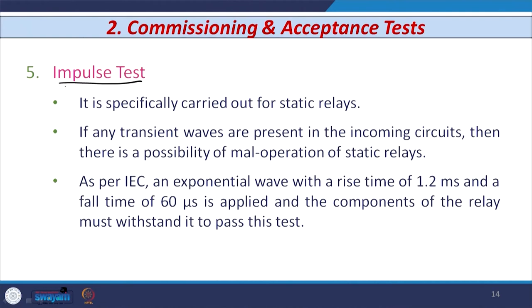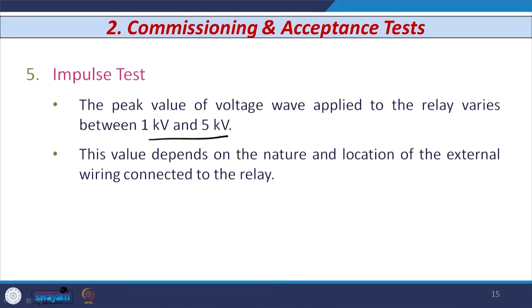The fifth type of test is known as the impulse test. This is a special test carried out on static relays — it is not performed on electromechanical relays. If any transient waves are present in the incoming circuit, there is a possibility of mal-operation of the relay, so this test is carried out to avoid that. An exponential wave with a rise time of 1.2 milliseconds and a fall time of 60 microseconds is applied. The peak value of the voltage wave can vary from 1 kV to 5 kV, depending on the nature and location of the external wiring connected to the relay.